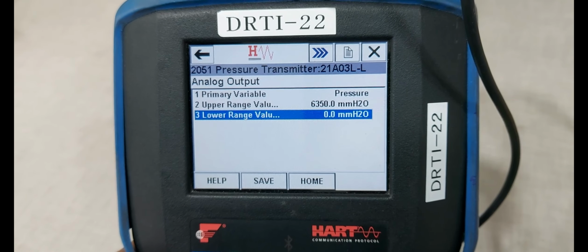Next we are doing the display setting: configuration menu, guided setup and the configuration of display. We enable the percentage of value. Actually level is showing for the percentage value. We select it, then on, enter and send it. There is already transmitted. The transmitter shows the percentage value and mm H2O value. This is the percentage value. Select it to home menu. Okay. Next we are doing the service tools.